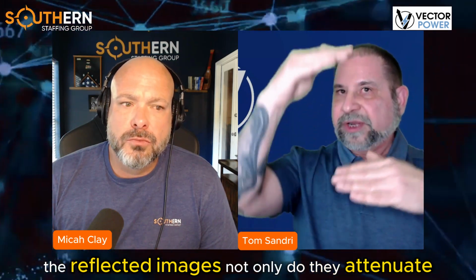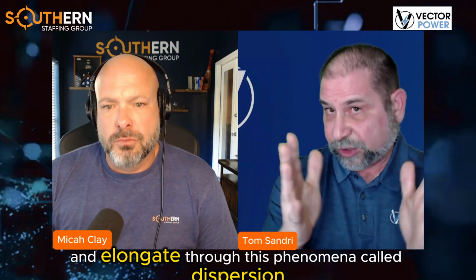Another aspect is called dispersion. As the cable starts to absorb this energy, the reflected images not only attenuate, but they stretch out and elongate through this phenomenon called dispersion. So when you're trying to meet a factory specification of like 5 picocoulombs, that's accomplishable the way they do it in the factory, where they're not worried about doing mapping, and they're doing it on controlled, shippable lengths of cable.